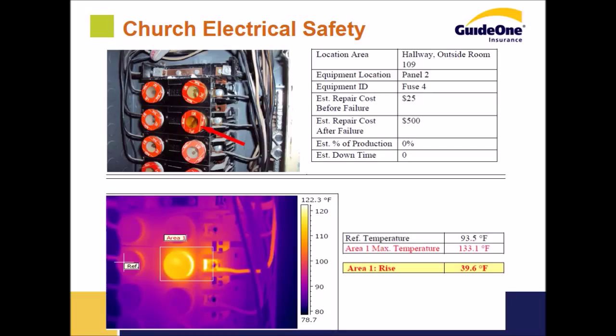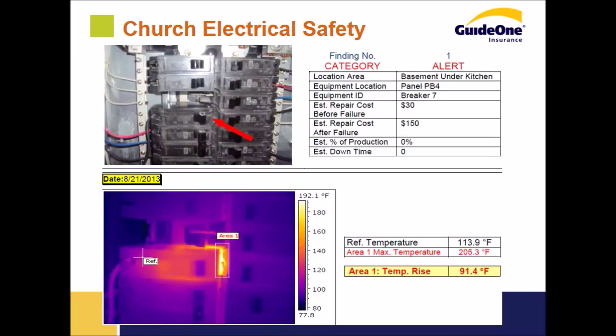An IR study is a very compelling piece of information. It graphically shows areas of concern, and it's the temperature we're watching for—a higher temperature indicates a partial or overload condition, or a bad connection. With the churches we've performed this service for, we've found them very receptive to our recommendations and they've made the appropriate changes to their systems.